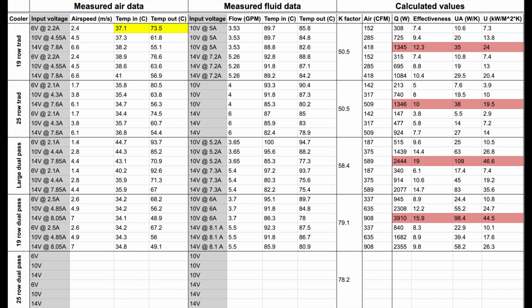The temperature measurements that we took, this is all a snapshot in time, so it was these input temperatures from the air. So the air input was 37.1, that's pretty much ambient air, and then the air leaving the exchanger was the 73.5. On this side, we see the water. So the water entering was 89.7 degrees, and the water leaving was 85.8. And then over here is the calculated output.